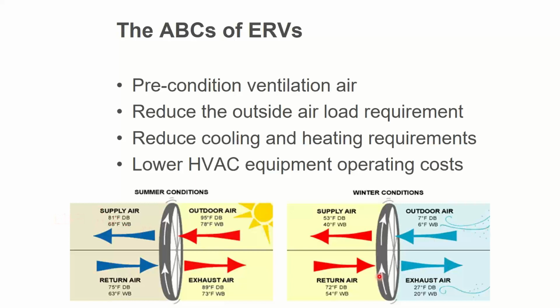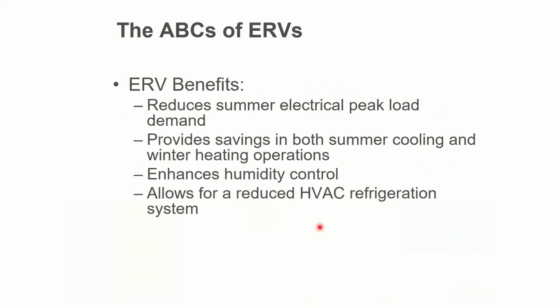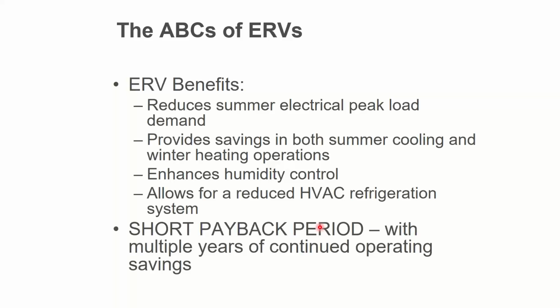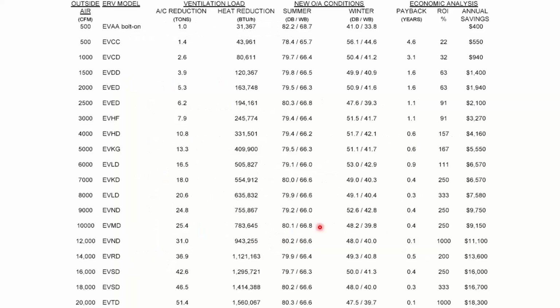And in the wintertime, it was the opposite. The heat and moisture from the exhaust air transfer their way into the outside air, thereby preheating me, and with the wet bulb from 6 to 40, pre-humidifying me. It's kind of sweet, right? So the benefits are energy savings, better humidity control, smaller HVAC equipment. I know that's weird because I work for an HVAC equipment supplier and I'm telling you to buy a smaller chiller, buy a smaller boiler, buy a smaller air handler, right? It's kind of weird. The payback period can be fairly quick.